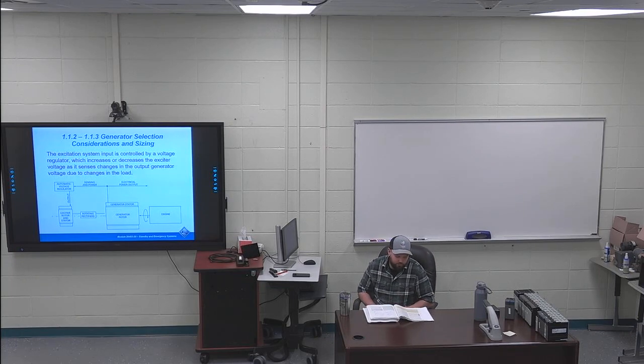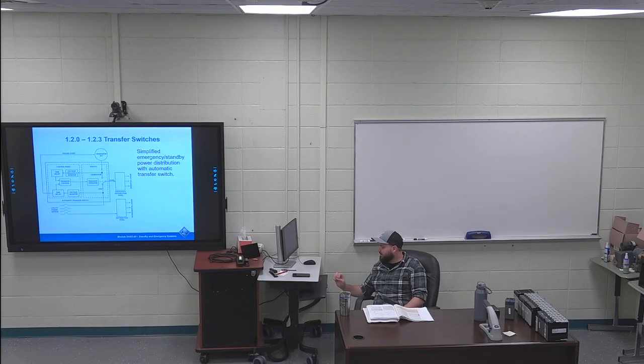Flipping over to 120, transfer switches. So, like I said before, all a transfer switch is going to do is switch you from normal power to emergency power. I don't have anything highlighted on page 6, but they do go through the functions of a transfer switch, and those 6 bullet points on page 6 wouldn't be a bad idea to read through while you're reading this chapter. On page 7, my first highlight is all the way in the bottom left of page 7, the first sentence of that paragraph that starts down there.